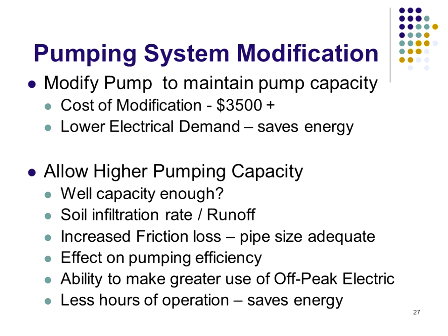So we have two choices if we want to go to lower pressure, because if we just lower the pressure, the pump output's going to increase. So we have two choices. One, we can pull the pump out of the well and modify it. Sometimes that means taking some stages off, and we'll talk about how a pump's put together here in a minute. But the cost of modification can be $3,500 up. That's kind of a low ball because you've got to pull the pump out of the well.